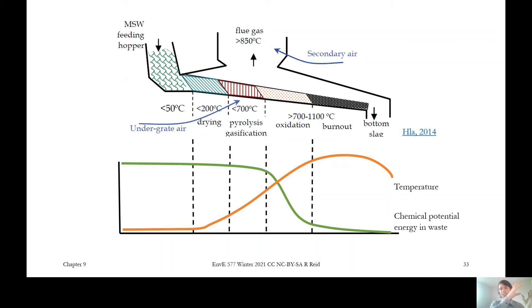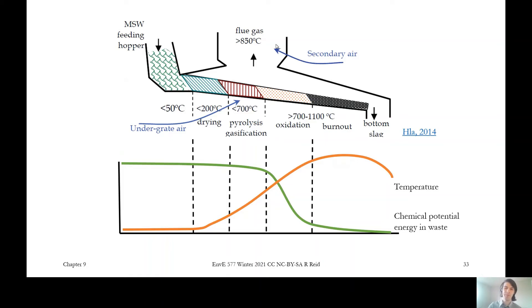A diagram shows what's happening as materials are charged into the combustion chamber and move through it. Wet waste comes in and the first stage is drying, using heat from already-burning waste to drive off water, which goes up in the flue gas. Next, pyrolysis and gasification of the solid material occurs. Once a critical mass of flammable vapors builds up, oxidation begins. Under-grate air is supplied mainly to cool the grates but also supports gasification, while secondary air from above burns out all the flammable gases coming off the waste.